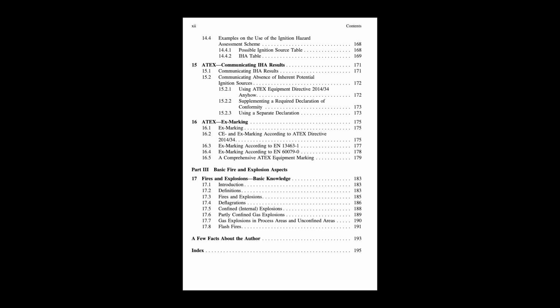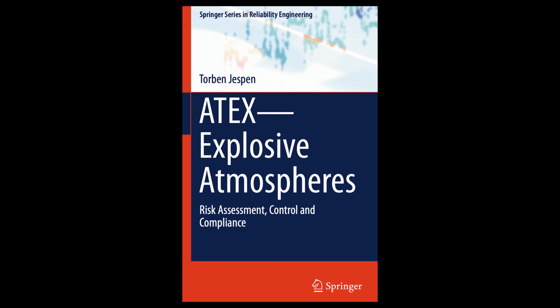But the guide adds a caveat. Yes, it warns that release conditions can affect density. For instance, a gas released under high pressure can cool significantly as it expands, making it temporarily denser than it would normally be at ambient temperature. So you need to consider the release dynamics too. Good point. Okay, that covers gases and vapors pretty well.